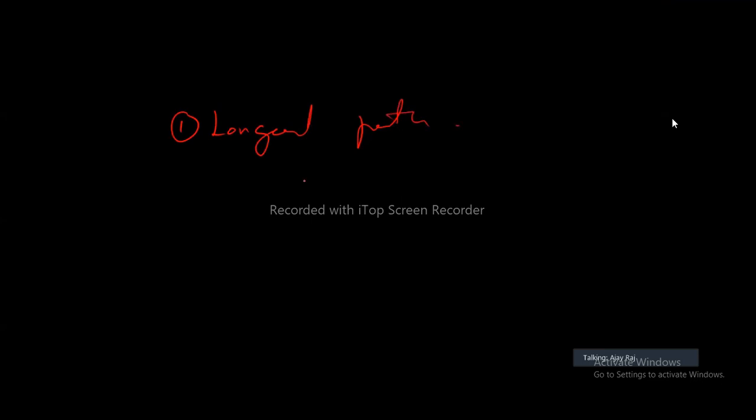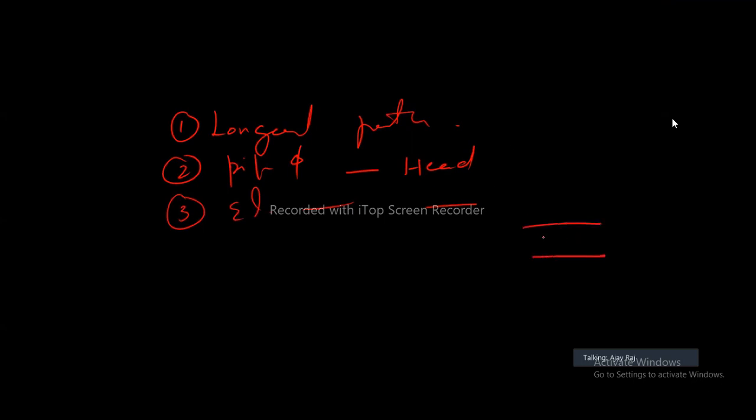Second thing is, as per pipe dia, I'll find out what is my head. Then I'll find out the equivalent length of all valves and add them all. So whatever I'm getting here is actually the head for my pump. I hope it is clear. Yes, sir.